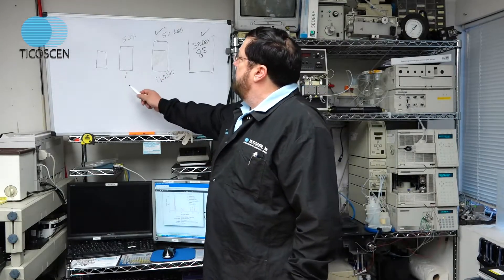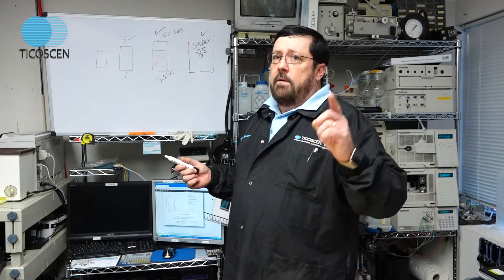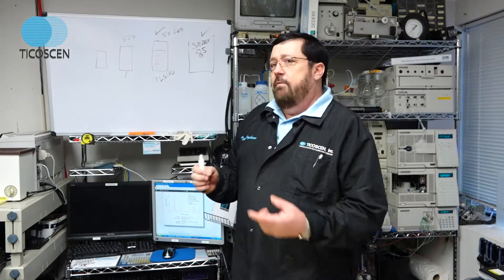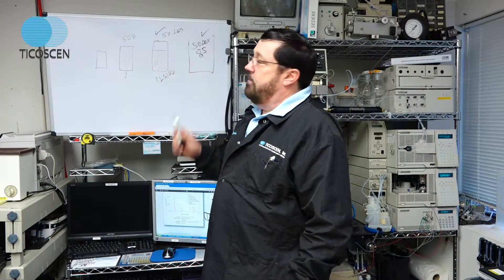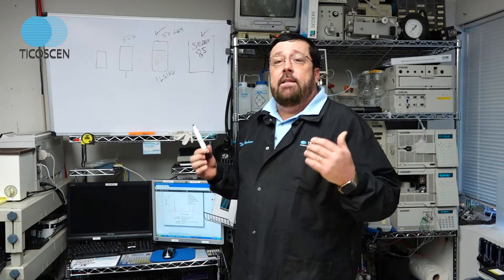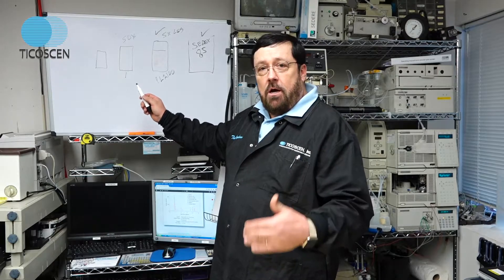There's a second pitfall to both the lower and higher sensitivity detectors: tolerance of turbidity. I have clients with lower-sensitivity detectors who have very dirty columns and dirty solvents, and these units will tolerate it. But when they transfer their method over to a high-sensitivity detector it fails, and they think something is wrong with the detector when in fact they just have a very bad methodology and haven't cleaned up properly. You can hide the truth by working with a lower-sensitivity detector — it'll tolerate your turbidity issues.